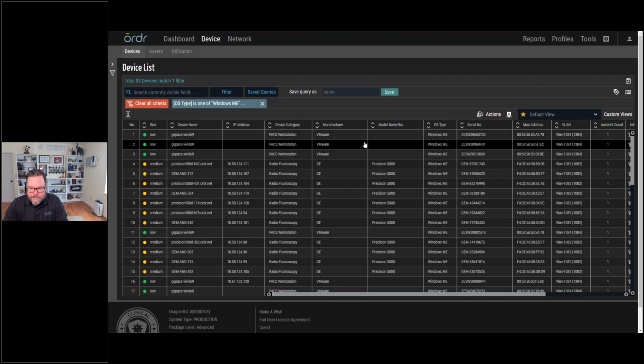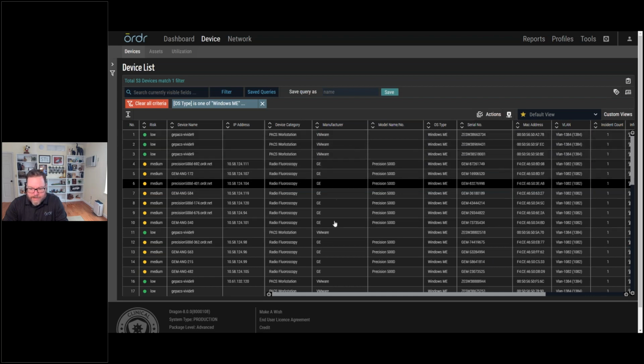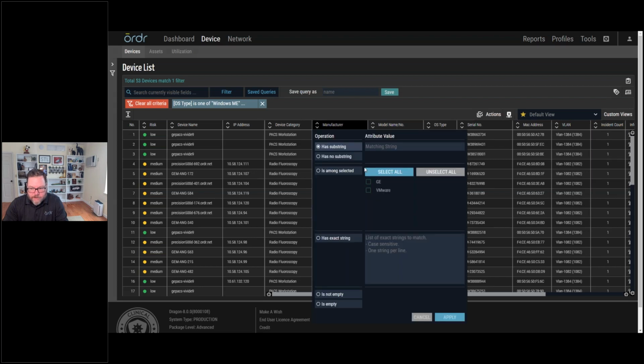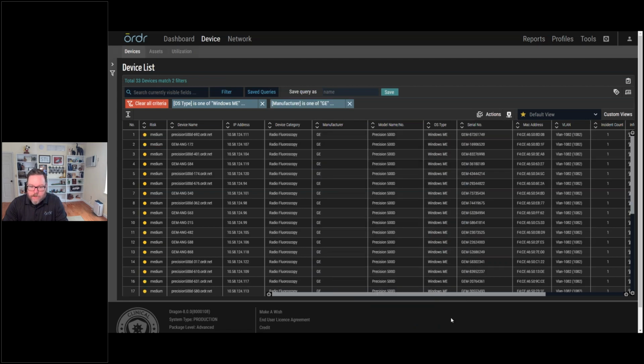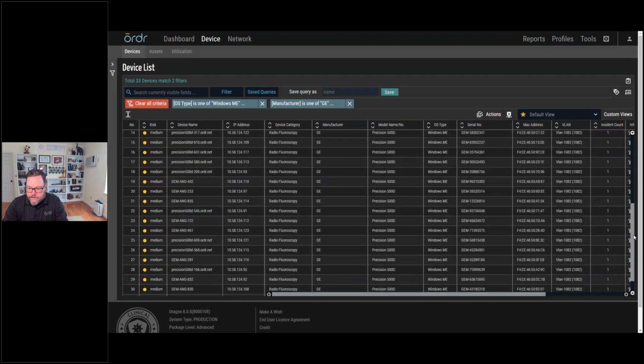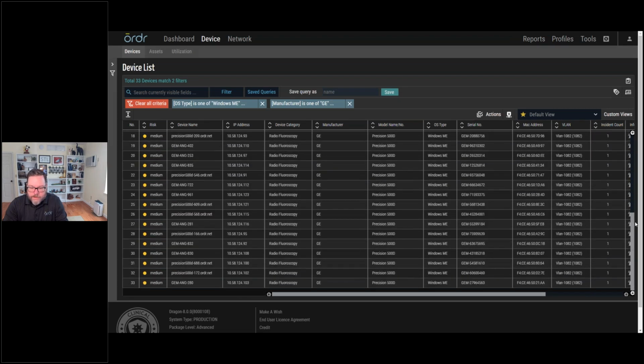You can see some of these devices don't have models, but they all appear to have a manufacturer. So with that, let's look at the manufacturers. Our two options are VMware, which doesn't sound like a medical device to me. Sounds like something IT should be addressing. And GE. Well, that's definitely a medical device. So now if we look at GE and apply that filter, we're down to the 33 devices that were referenced in the email. So we have 33 Precision 500Ds on the network that are all running Windows ME.